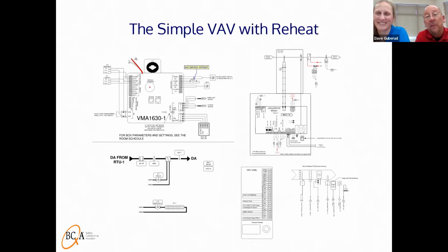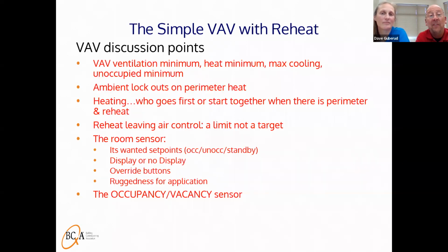Okay. So something simple as a VAV box, there's a lot going on with this also. So I think we want to just do a little deeper dive on this. Control contractors have oodles and oodles of set points. And sometimes they even have little package solutions, and depending on what mode you don't even think it's going to operate in, it touches that set point and puts it to some crazy CFM that no one's ever seen before.